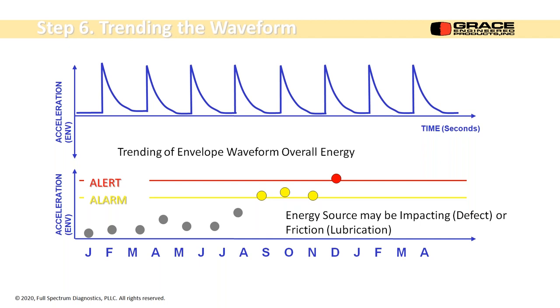This we can trend. So we put it through our peak detector and we can trend the level that's coming out of this. And I made it look pretty variable, clean, but it can be jagged and different. So we'll trend this over time. And when it goes into alarm, there's two possible things it could be. It could be either impacting due to a defect in the raceway, or it could be friction from lack of lubrication. So either way, we probably give it a shot of grease and see if it settles down.